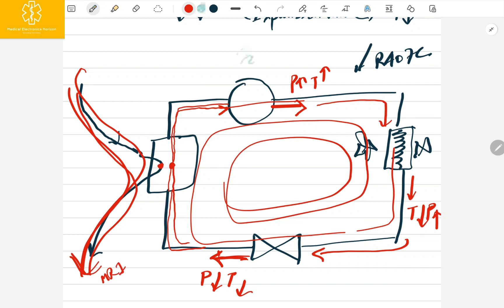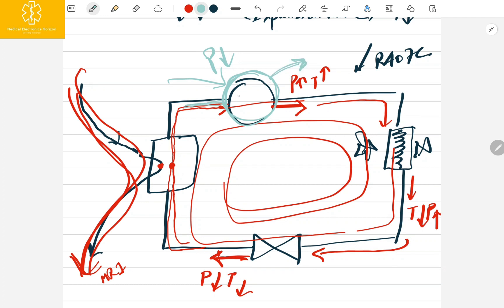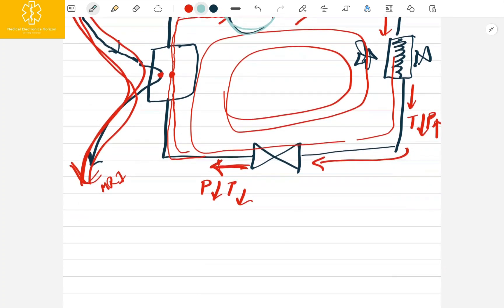One more important point: in any compressor, the output is called the discharge point and the input is called the suction point. At the suction point the pressure is low — you may have heard AC repair technicians use these terms. The gas coming out from the compressor has high pressure, which is why it is called the discharge point. The suction point is the inlet where lower-pressure gas enters the compressor.